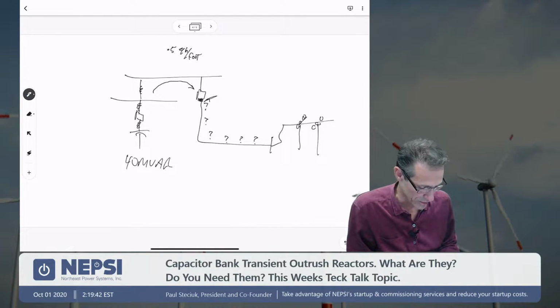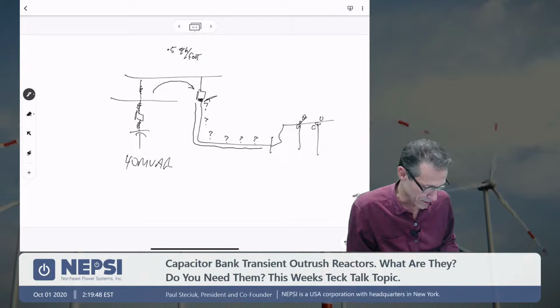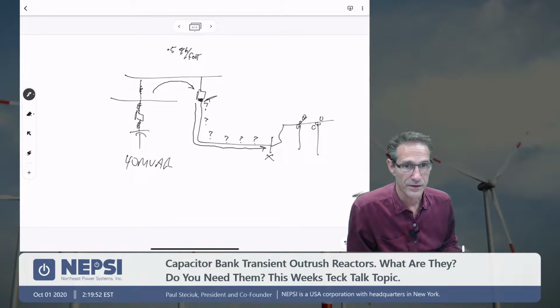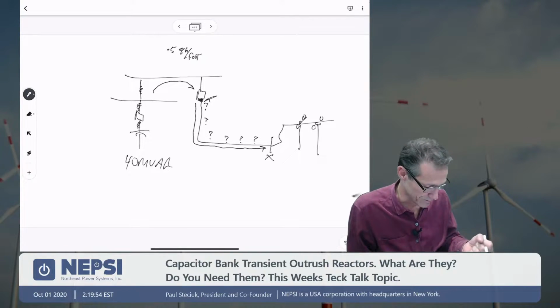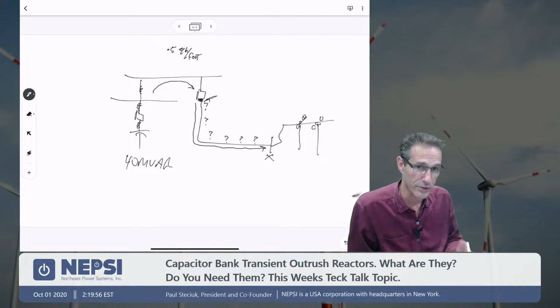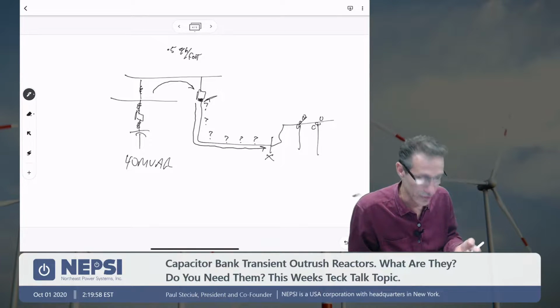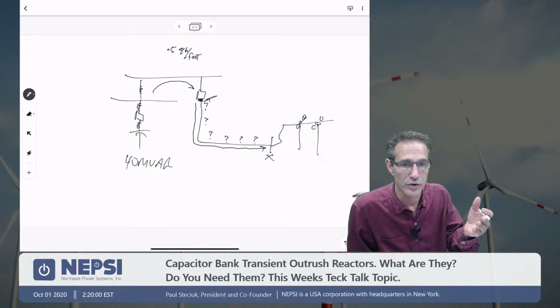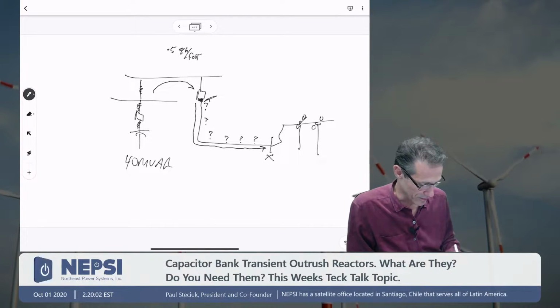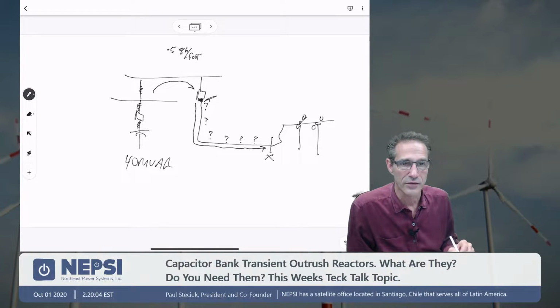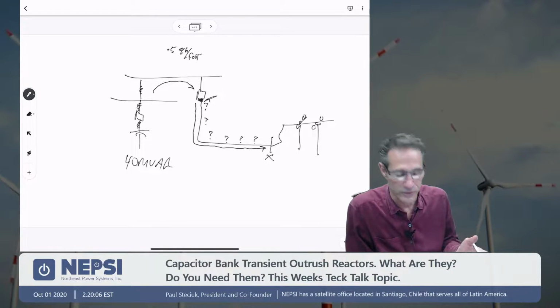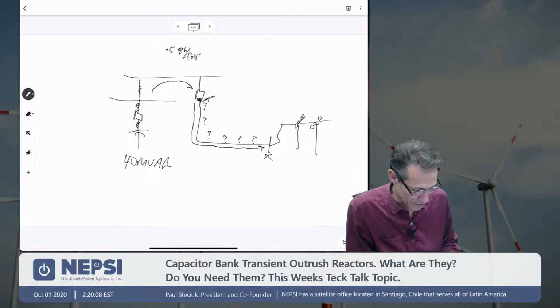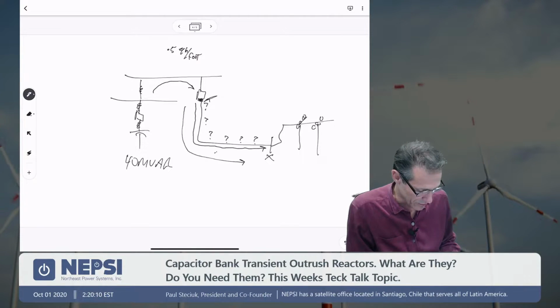You would then move along this cable and ask, where can I have a three-phase fault? In my opinion, the first location is here. That might be a pole, a place where you pull the cable through, or a riser going up a pole, but somewhere out there. Is it realistic at that point to have a three-phase fault or a phase-to-phase fault? So it's the inductance along this full length that you want to consider.